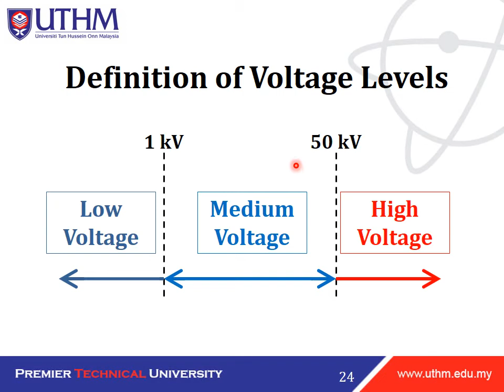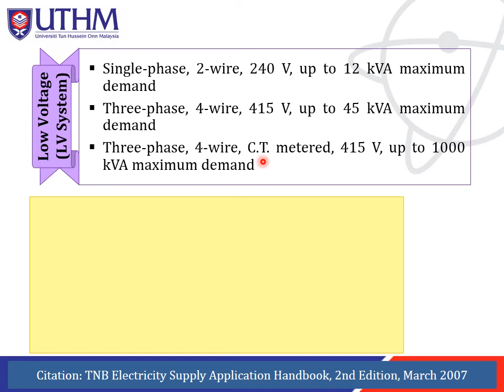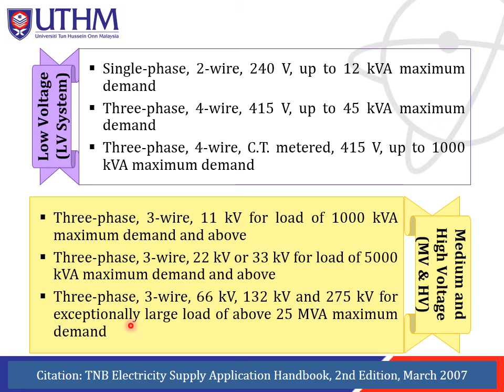Okay, for the low voltage system, it can be single phase, 2-wire, 240 volt up to 12 kVA maximum demand, or it can be 3-phase, 4-wire, 415 volt up to 45 kVA maximum demand, or it can be 3-phase, 4-wire, CT metered, 415 volt up to 1000 kVA maximum demand. Meanwhile, for medium and high voltage, it can be 3-phase, 3-wire, 11 kV for loads of 1000 kVA maximum demand and above, or it can be 3-phase, 3-wire, 22 or 33 kV for loads of 5000 kVA maximum demand and above, or it can be 3-phase, 3-wire, 66 kV, 132 kV and 275 kV for exceptionally large loads of above 25 MVA maximum demand.